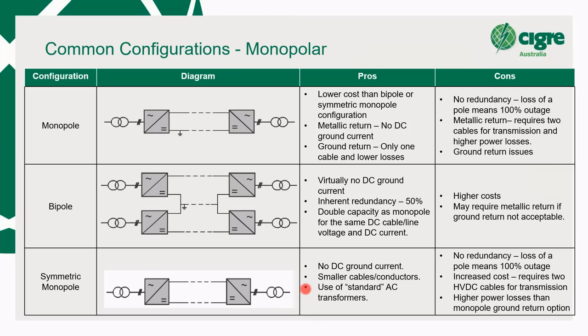If you compare it to a monopole for the same megawatt level, it has half the current. So that allows you to get away with smaller cables, smaller conductors, perhaps. It suffers the same problem as a monopole, though, as in you get a fault in the cable or the converter and you are 100% out. But it also has this benefit of you being able to use standard AC transformers instead of HVDC converter transformers, where the DC voltage stresses and the design are actually quite complicated and therefore quite expensive. And there's a relatively small number of manufacturing facilities that can build them.